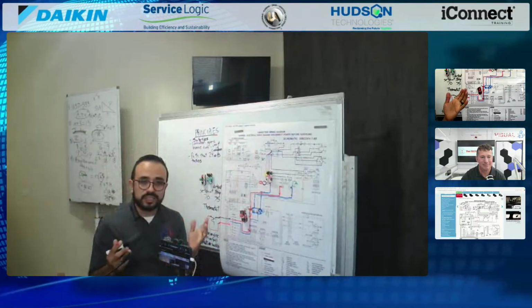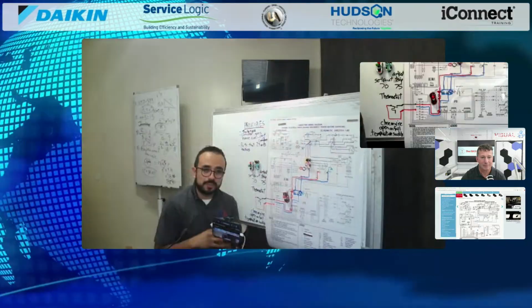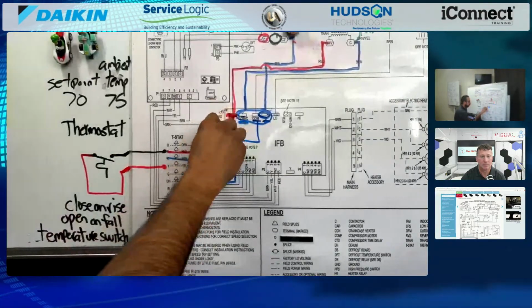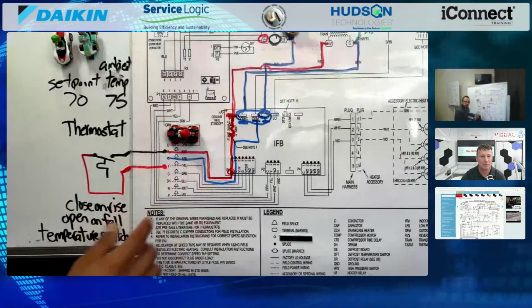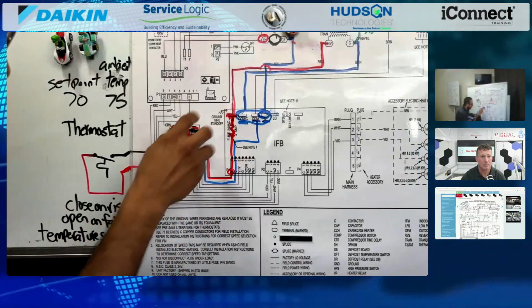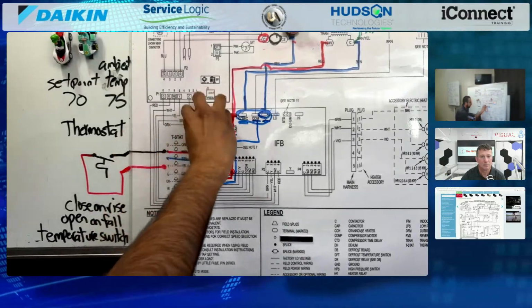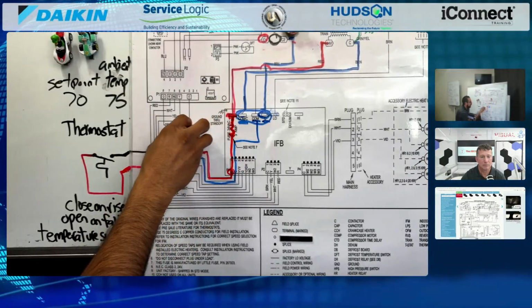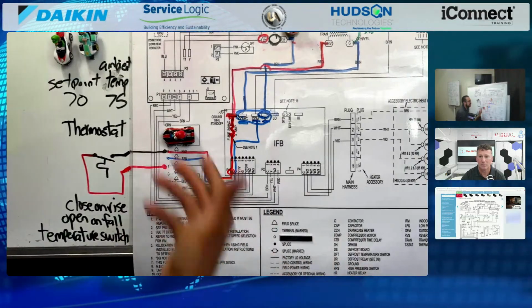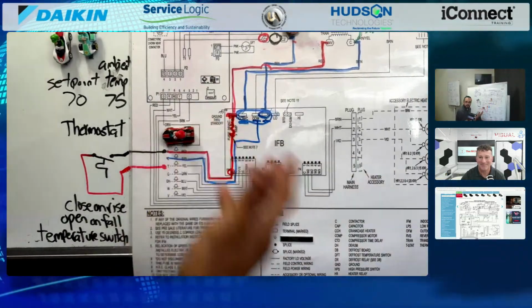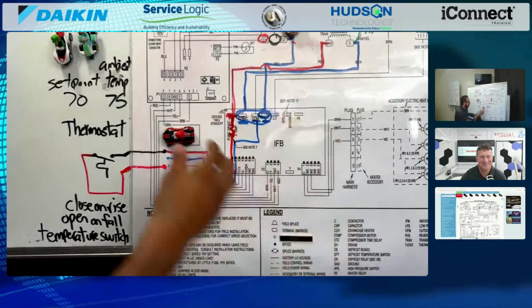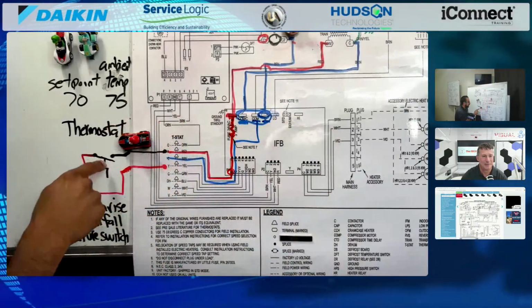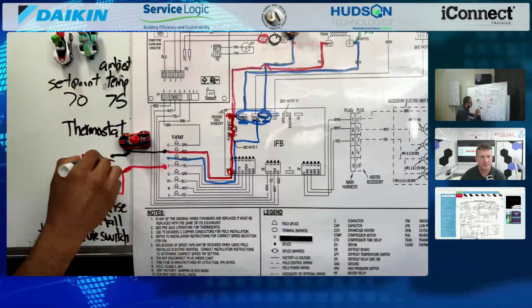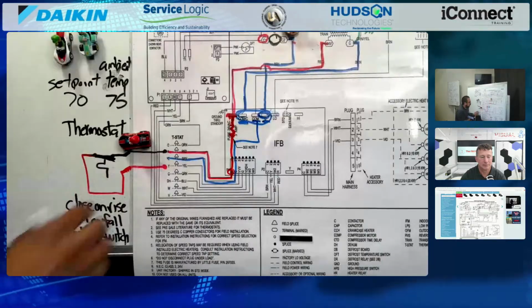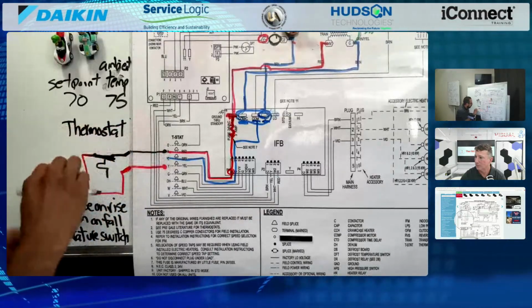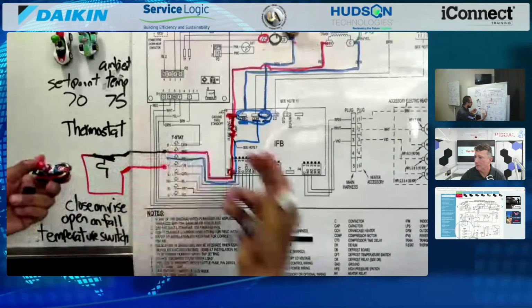Let's say that set point is 70, the ambient temperature is 75. So then what Mario does, Mario goes here. Mario is still the red, it hasn't changed, he's still the red. So Mario's going, all right, I'm almost close to getting that rehab help, to not fight with the other gang member, to get therapy with my wife at the therapist, whatever it is, I'm almost there. He makes it to the thermostat. I have a call for cooling. The switch closes, so now it's touching each other, okay? And so Mario then comes, but he doesn't go back on red. The red is just to power up the thermostat.